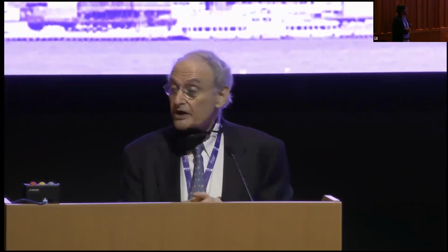Just like that early debate on the floor of the RSNA, that's still a vexing issue. The higher the field you go, the higher, in principle, the signal to noise can be. And so for the small things, like the remarkably beautiful pictures you saw, I think that was 17 tesla, that's great. And we'll hear more about how we can even go higher. But the higher you go in field, you have other problems. The relaxation times change. T1s tend to get longer, which means that you otherwise might get a weaker signal. T2s get shorter, so again, you have less time to take your data.